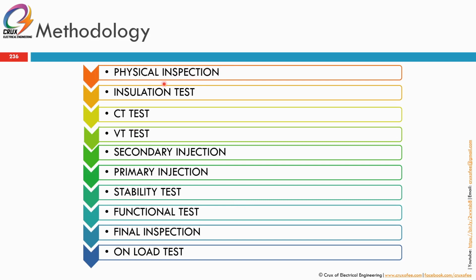So we will start with physical inspection, looking at the visual inspection of the equipment, whether all the connections have been torqued properly. Is there any brace or cut on the cables or on the termination, and so on. So it's more physical inspection, more on the visual inspection. And there are some tests included in the physical inspection, such as the torque check and the cable pull test. What else? Physical, that's mainly it.